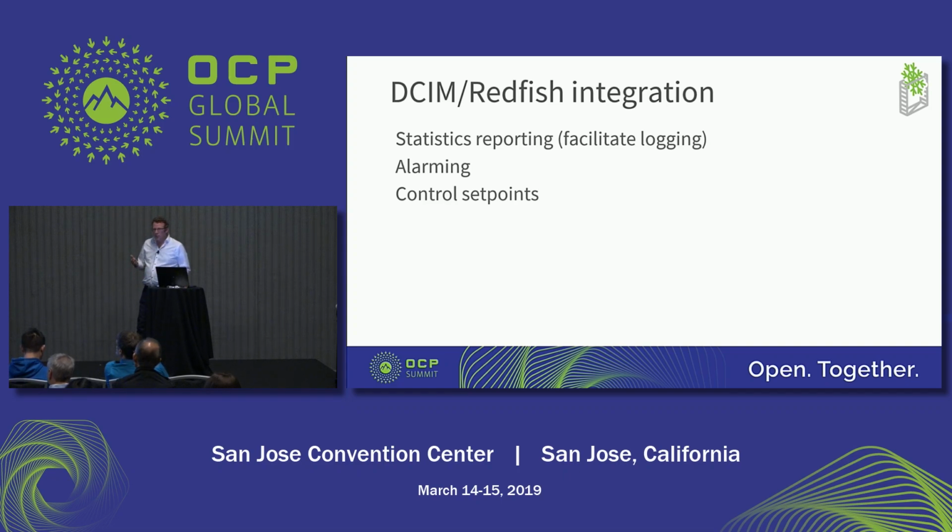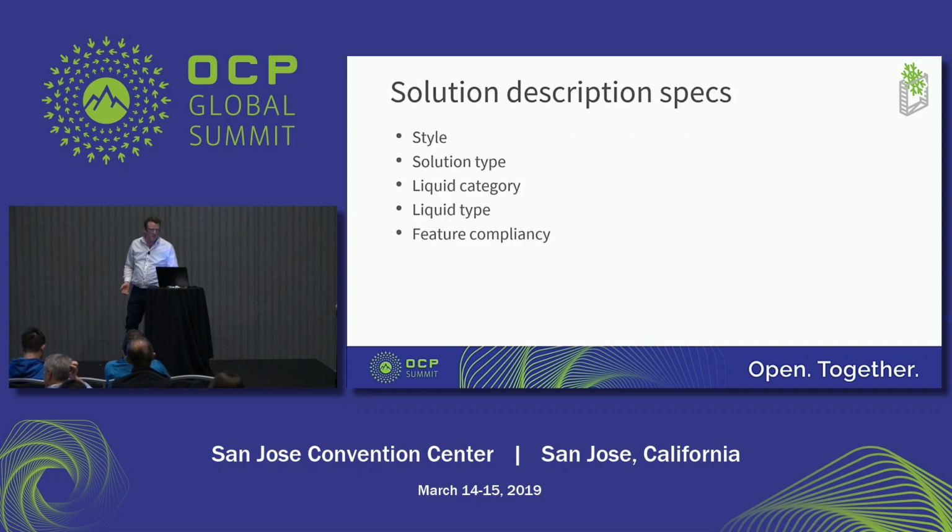One other thing that we've discussed that is also required is that we have a completely different type of compute environment, a different type of racks, which need to be managed. They need to be able to hook into any kind of data center infrastructure management. So we've defined a very basic standard for that, which is based on Redfish, because that's the standard within OCP. That allows reporting features, logging, alarming, or control set points. It allows anyone to start building upon the management system to increase functionality and interoperability with existing OCP environments.